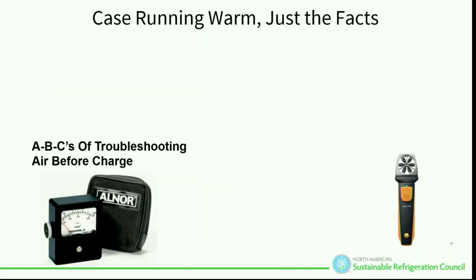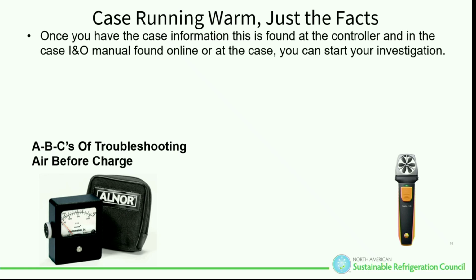All that stuff is out there somewhere. The ABCs of troubleshooting. No, I'm not talking about Sesame Street. I'm talking about air before charge. That's what you're going to check first. Airflow is most important. Once you have the information, and this is where you get it from, a lot of the manufacturers have IOM manuals, installation operation manuals. All that spec will be there, what your airflow is supposed to be.